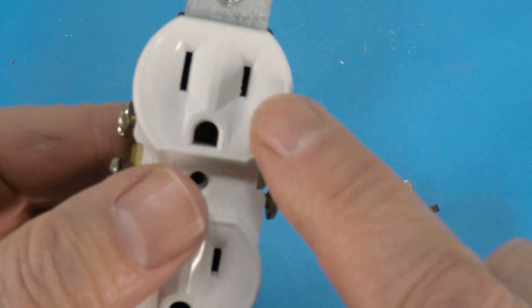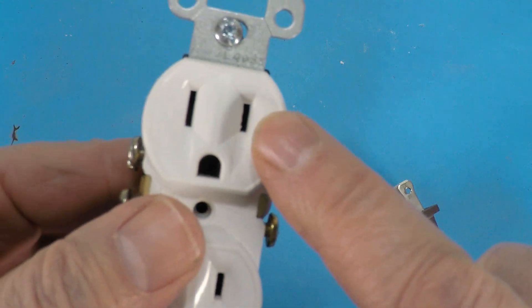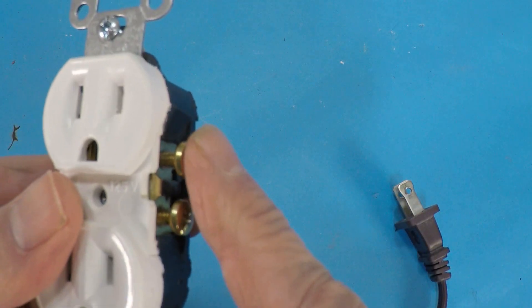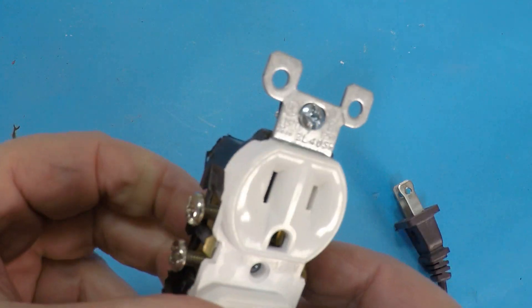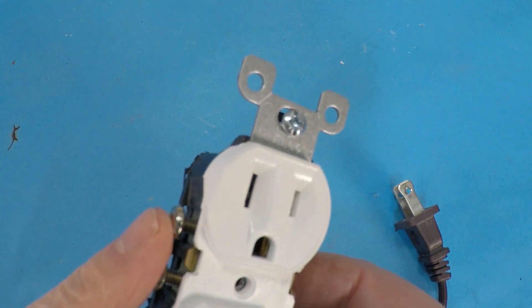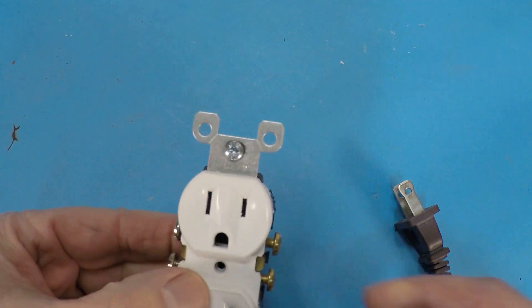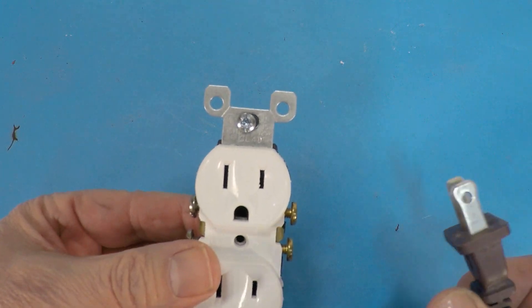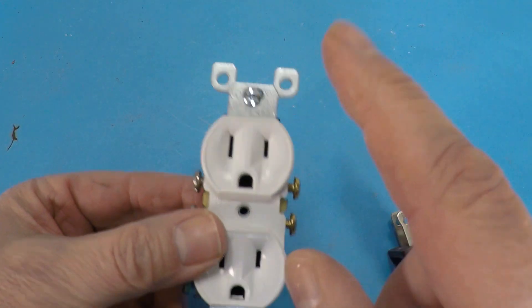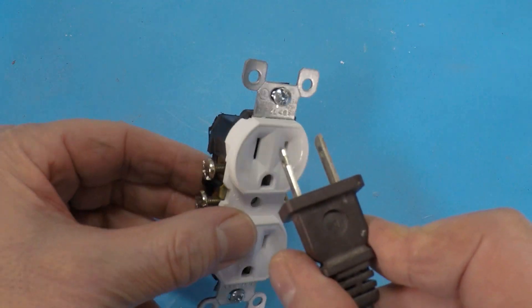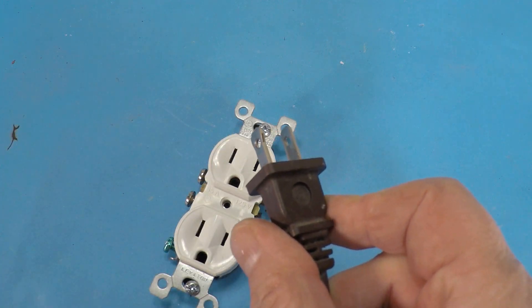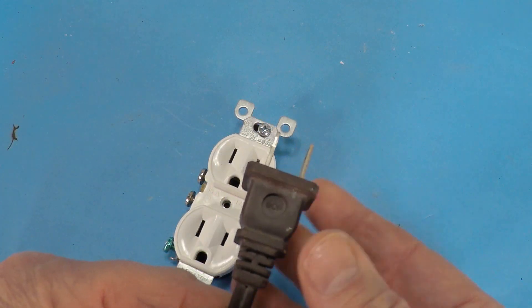The gold, which corresponds to the short or small hole or opening in your outlet, is where the power comes in. The black wire, the hot wire. And the silver side, which is the large side, is for your neutral, so it's to make sure that everything going from the breaker panel through the wire to your receptacle and right back to your device is all neutral on one side and all hot on the other.